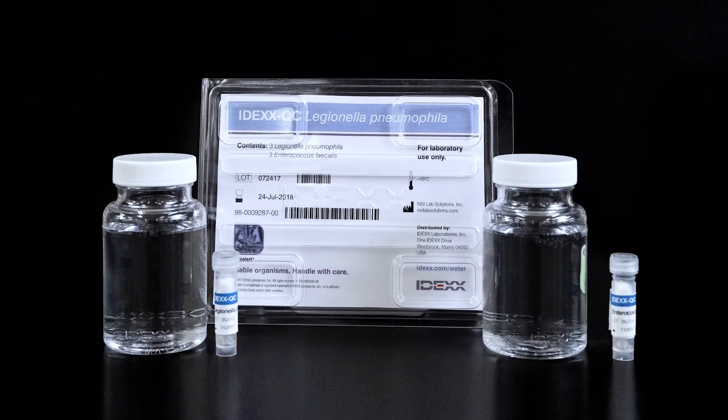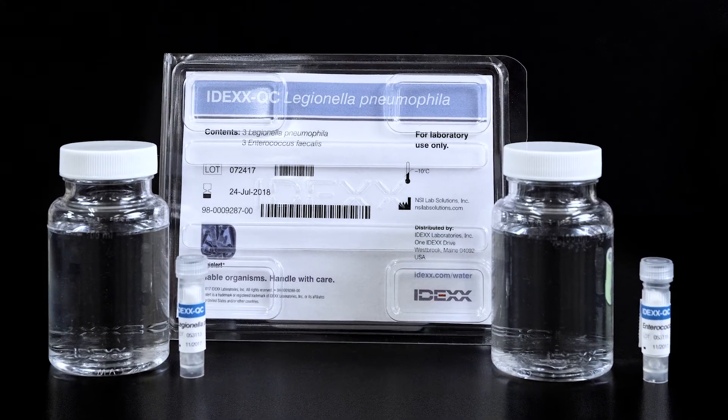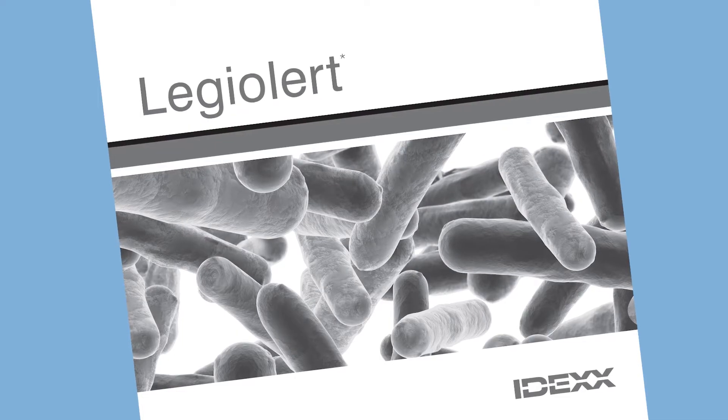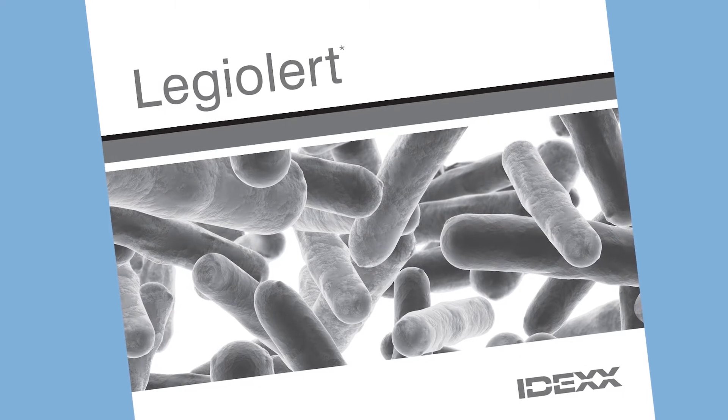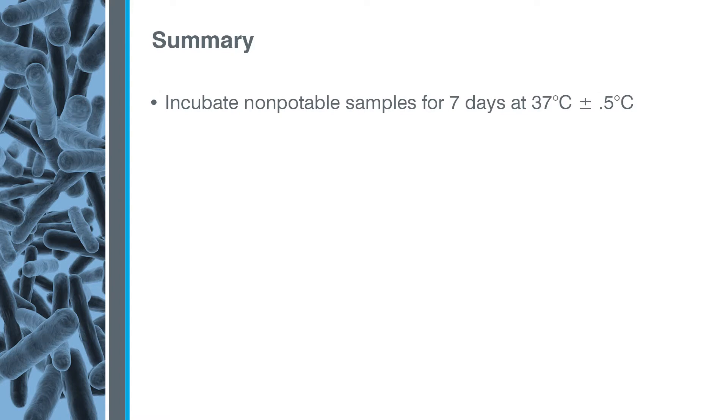IDEXX recommends that you run a quality control procedure for each lot of Legiolert tests. You will find the quality control procedure in the Legiolert product insert. Remember, incubate non-potable samples for 7 days at 37 degrees centigrade, plus or minus 0.5 degrees.